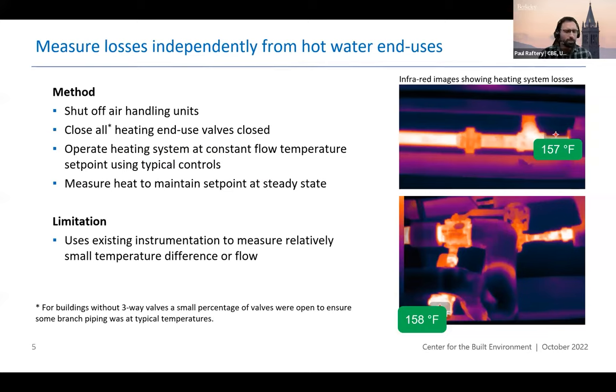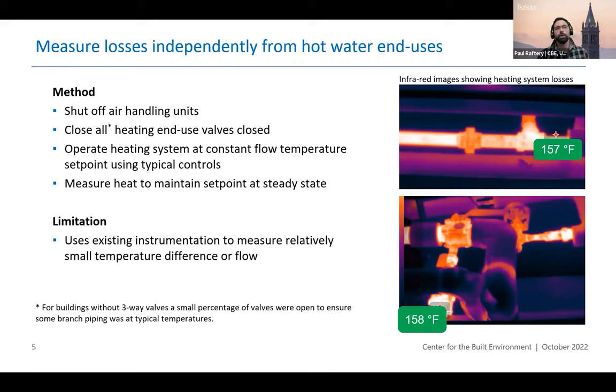We developed a method where we shut off all of the end use equipment like air handling units during unoccupied periods, close all valves on reheat coils and baseboards, and then operate the pumping system at the same temperature, pressure, and flow set points as normal. We measure the heat required by the boiler or district hot water system to maintain the hot water supply temperature set point at a constant rate and average that over time. One limitation is that we were using existing instrumentation in these buildings, which was of variable quality — in some cases very high quality, in others older equipment.